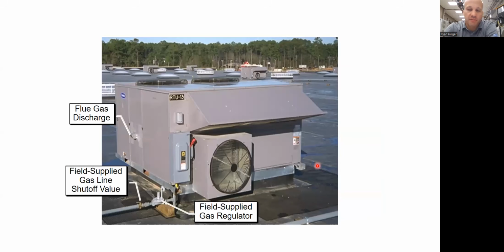All right, other stuff that's going to be involved in these units when you're looking at them visually on a roof, so you know what you're looking at. If you want to know how it's heated, if you see a gas line coming to it, and you know it's a gas line because not only is there a pipe coming to the unit, but there'll be some kind of gas regulator external to the unit. So when you see that pipe and that gas regulator, you know you have a gas-fired unit. That's how he's doing his heating.